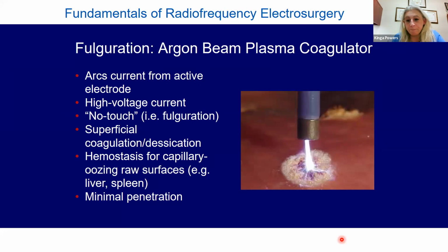Remember that argon gas is actually a gas and it's emitted. It helps clear off some of the blood on the surface, but it can also go into the peritoneum if you're doing laparoscopic surgery or endoscopy, increasing the gas content in the enclosed space. So you have to suction or release the gas, and it can also cause gas embolism. You have to be cognizant of that.